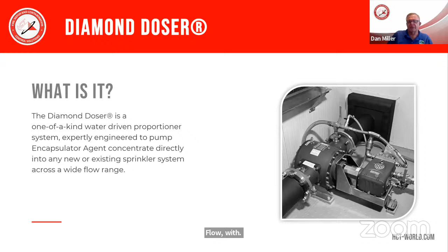The Diamond Doser is our premier volumetric water-driven proportioner. It's placed into the riser, and the water flow turns a water motor, which turns a small pump that pumps in the agent at a very exacting amount into the riser. This gives you a good wide range of flow with no variance in concentration, which stays very stable throughout the wide range of the Diamond Doser.